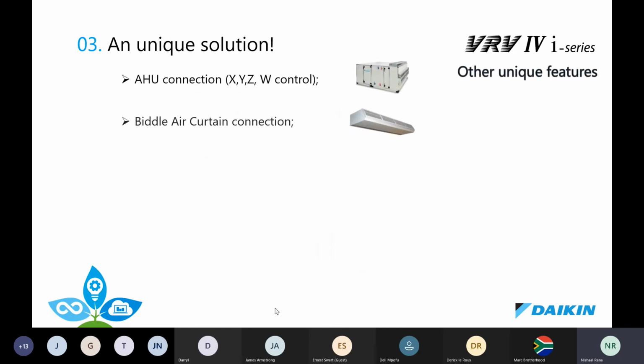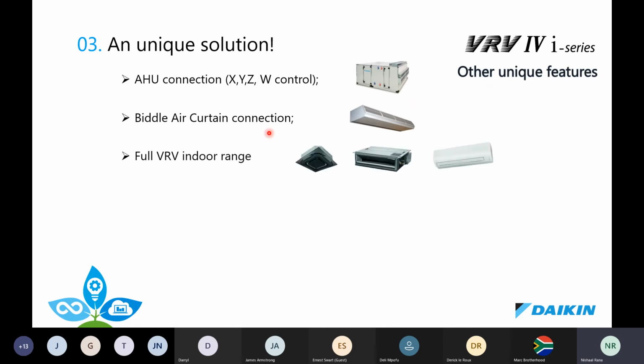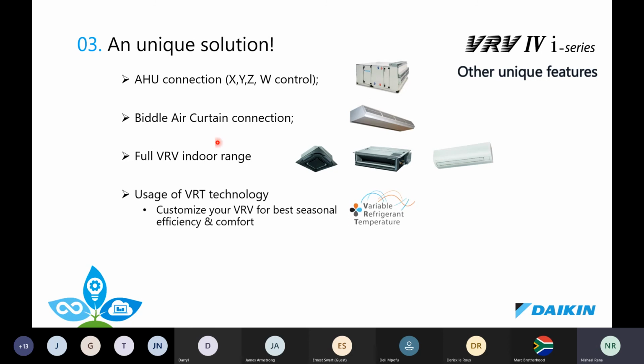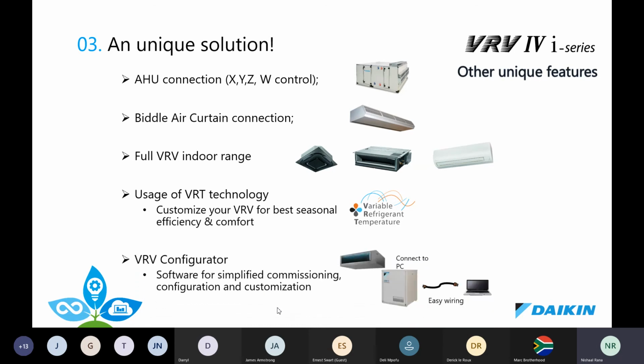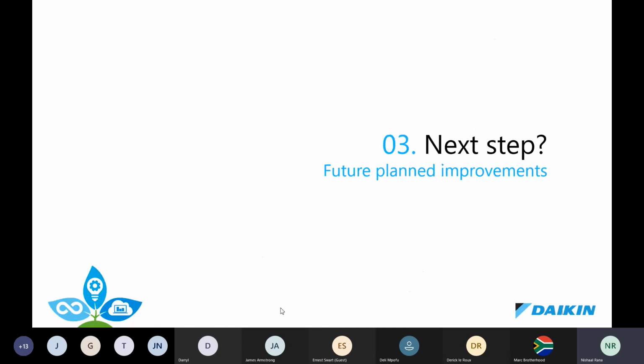Other unique features: you can connect it to an AHU. We don't unfortunately bring the air curtains, sorry, I should have removed that. And your fully inverter VRV range, so you can connect it to a very small AHU if you had to, and you can connect it to our normal VRV range that you would normally use. It also uses the VRT technology that I explained earlier. It also connects to the same software, the VRV configurator, so no problems there.